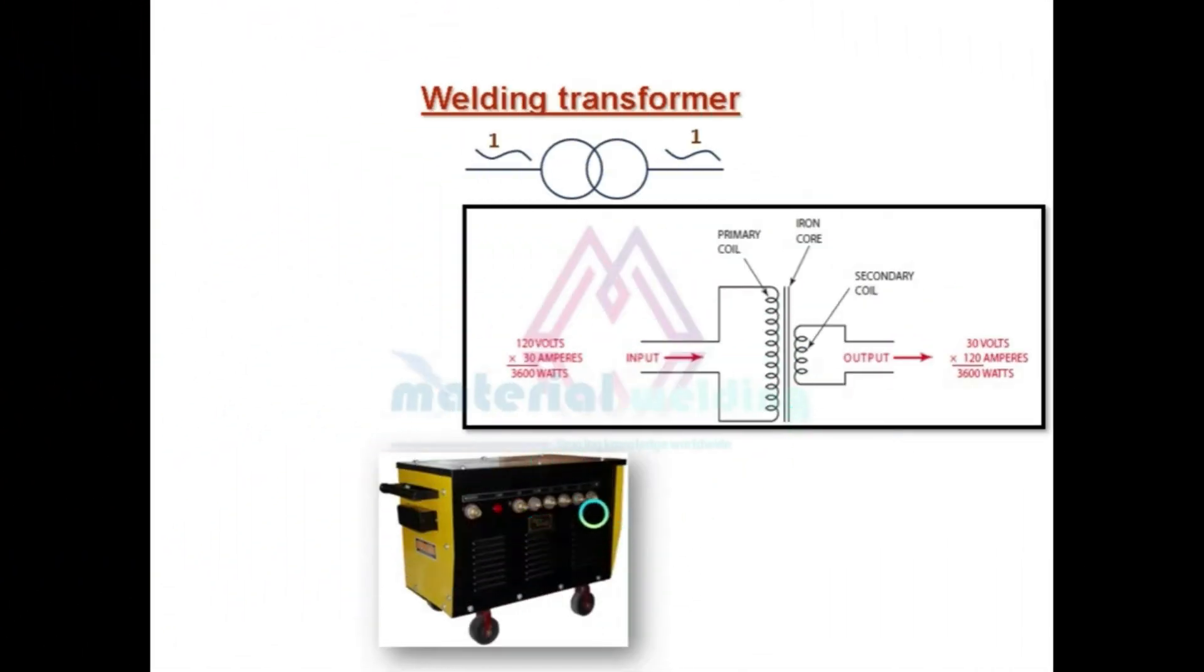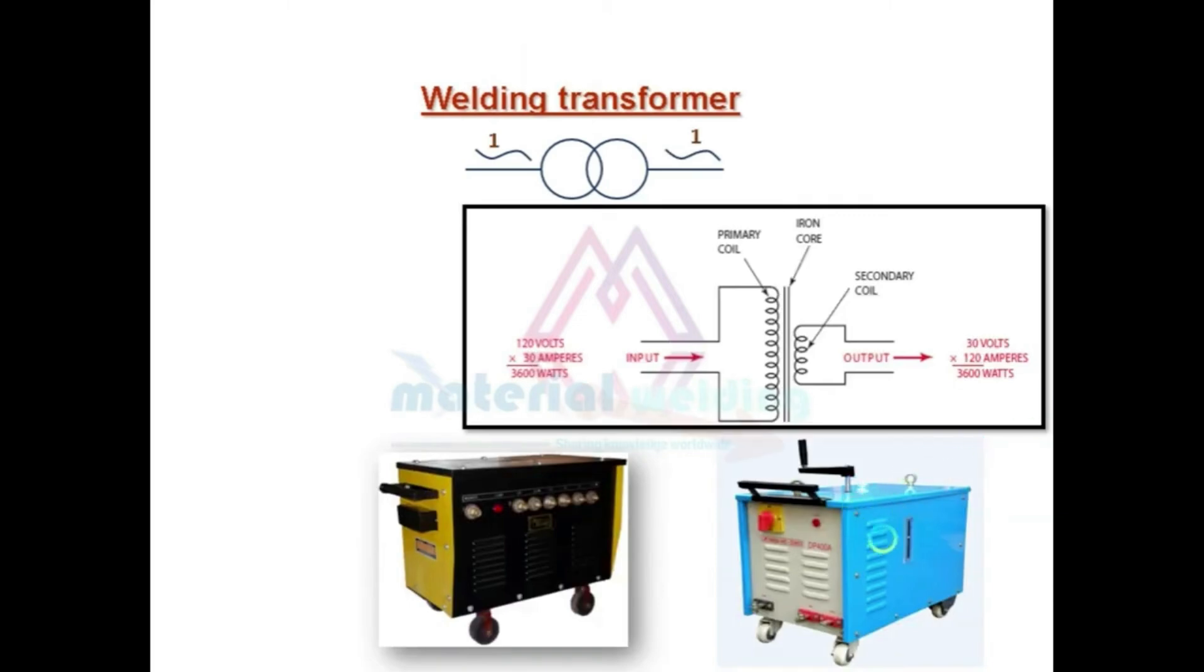The picture shows how a transformer type welding power source looks like. One way to identify is the multiple connectors available on the front side. As there is no current adjustment controls, these different connectors are connected to the secondary wiring of the transformer. So when the number of secondary wiring turns varies, we get different output current for welding operation. Some type of welding transformer use a rotating handle for this purpose, as you can see in this picture.